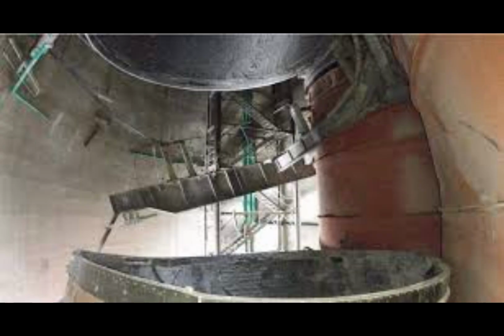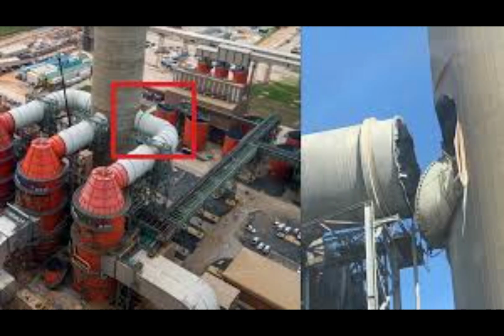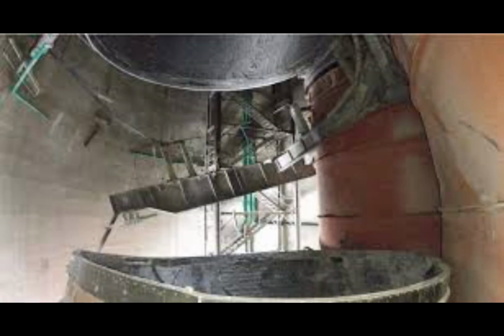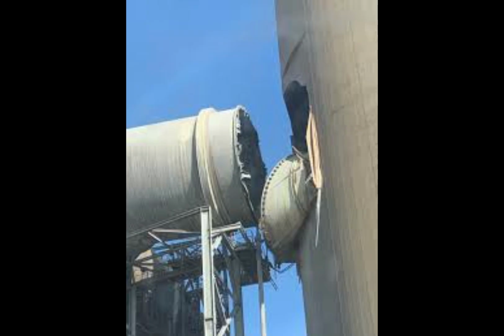Technical issues such as boiler design, high temperatures that the spray water cooling system could not cope with, fabric filter plant, excessive wear of bags, resulting in blockages. Coal mills failed to meet operational requirements, which necessitated a doubling of servicing, flue ducts, and resultant damage to chimney. A wet flue gas desulfurization system between the boiler and chimney, intended to remove harmful sulfur dioxide from emissions at its first desulfurization stage, where non-functioning baghouse filters supposed to capture fly ash from emitted gases failed.